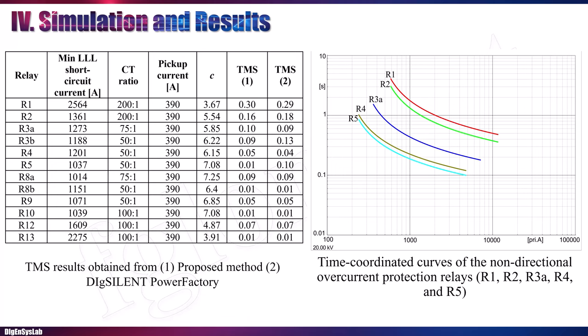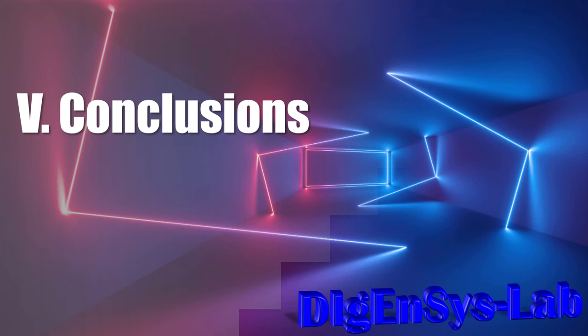We also used DIgSILENT PowerFactory, a well-known software with automatic overcurrent protection coordination capability. We compare results between column one — the proposed method — and column two — results from DIgSILENT PowerFactory. The results are almost similar, with discrepancy below 0.01. The time-current diagram shows coordination between several relays on the feeder, validating that the proposed method creates proper time-current coordination.